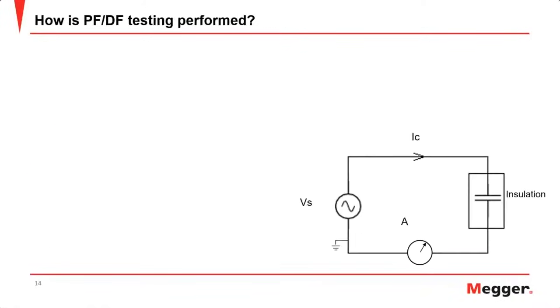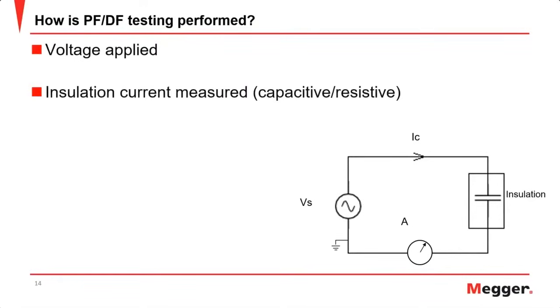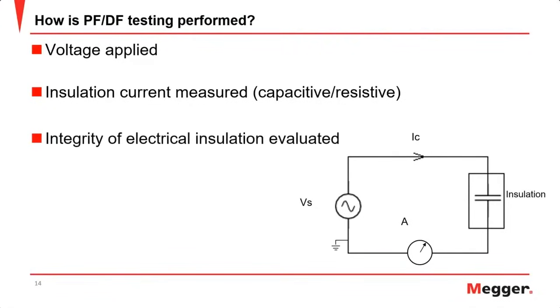And how is a power factor test performed? You connect your high voltage source to one side, you apply that voltage, you will then measure the current through the capacitor, looking at the capacitive and the resistive components there. And then you make your evaluation of the insulation based on that leakage current that is coming through that capacitor.